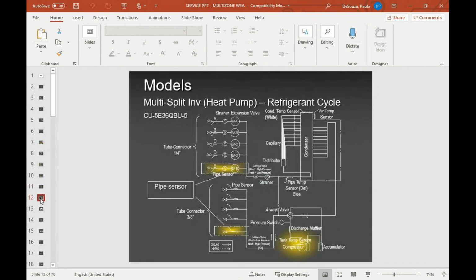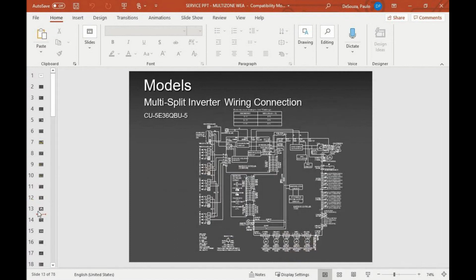That slide there shows, I know it's small on your side, but these are your indoor units: 1, 2, 3, 4, 5, because we're talking about a 5-zone, guys. So that's your indoor unit. Each and every indoor unit has its own electronic expansion valve. Okay? The electronic expansion valve will stay slightly open even when the indoor unit is not calling. That is designed for smooth oil return.